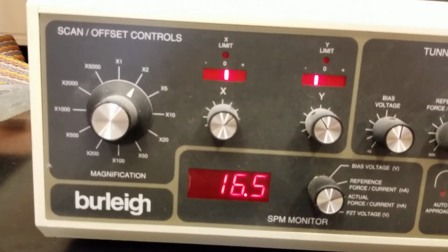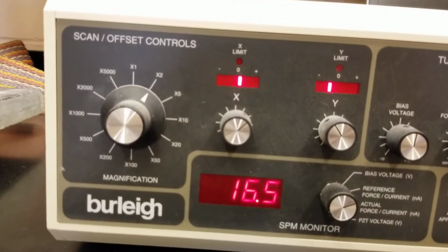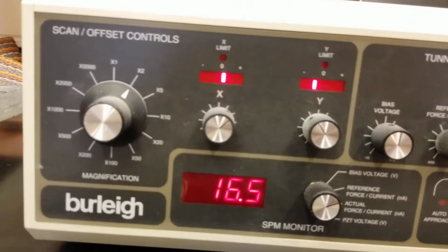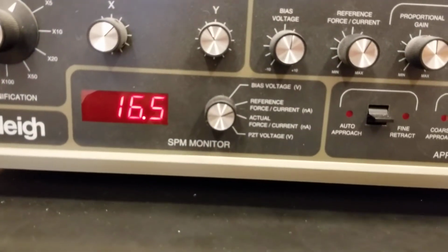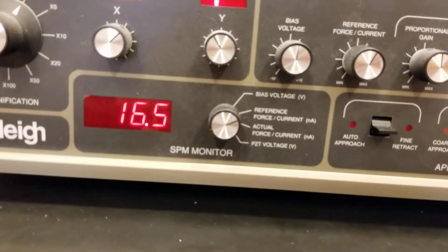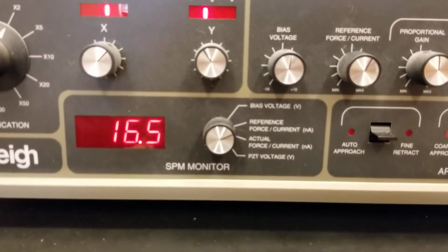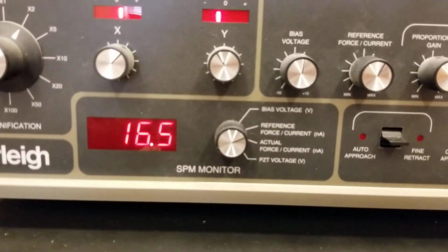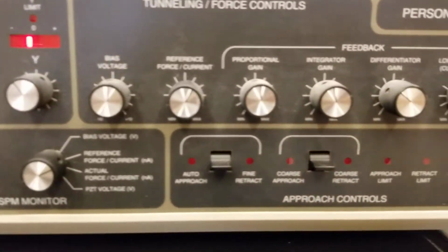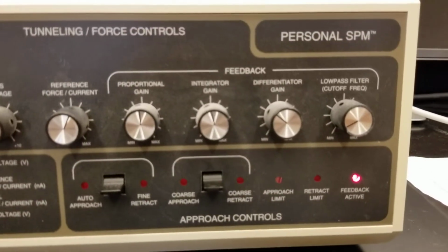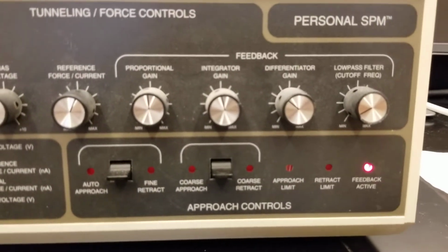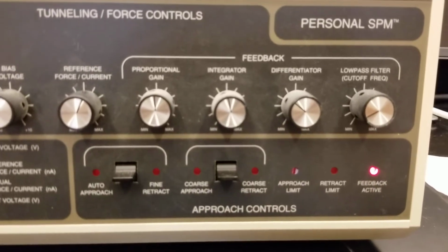On the controller unit of this device, we've got a magnification on the far left, just how much we want to zoom in. And down here is where we actually set the force, whereas the STM used tunneling current. This one uses repulsive forces as it scrapes across the sample. And then we've got over here the feedback, similar to the STM, that we can control how fast it goes up or down, away from the sample or towards the sample.